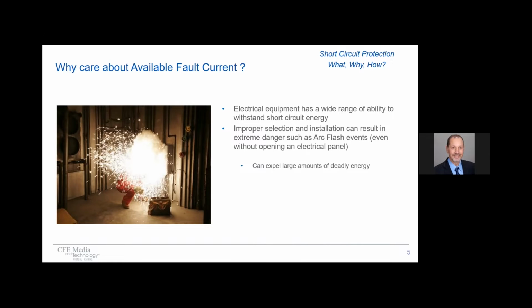It can expel large amounts of energy. Temperatures can reach very high temperatures, and it can throw projectiles. It can cause normally grounded surfaces to become live. Now, those are some pretty good reasons to care about available fault current, but what does a person do about it?